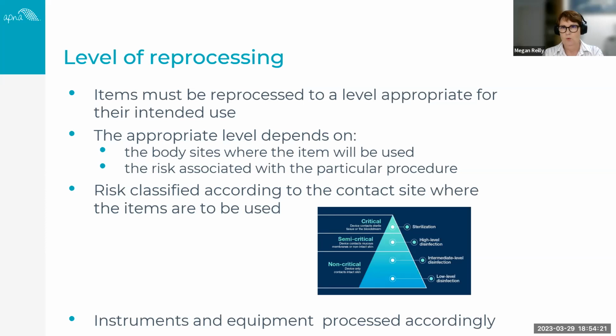Once we've done that, we can work out whether it's a non-critical device, a semi-critical device, or a critical device, and to what level we actually reprocess it. If it's a non-critical device, is it low-level or intermediate-level disinfection? When we get to semi-critical, it should be high-level disinfection, although high-level disinfection is an automated process, and it's in order to keep it safe, because we're talking about very strong disinfectants. So what we tend to do with our semi-critical devices is jump straight to sterilisation, unless they're heat intolerant or heat sensitive items. All of our critical items definitely need to be sterilised. In general practice, that tends to be steam sterilisation rather than some of the newer forms of technology that have come on the market and are probably quite difficult to manage in an office-based practice.